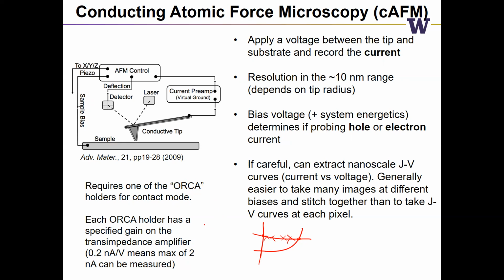The Orca holders can come in a couple of different ranges. So there's a 0.2 nanoamp per volt head. That's our workhorse one. So that means the maximum current that you're going to measure is 2 nanoamps, because the maximum voltage it'll read is 10 volts that you can read into the AFM controller. There is one that measures 20 nanoamps. So that's a 2 nanoamp per volt head.